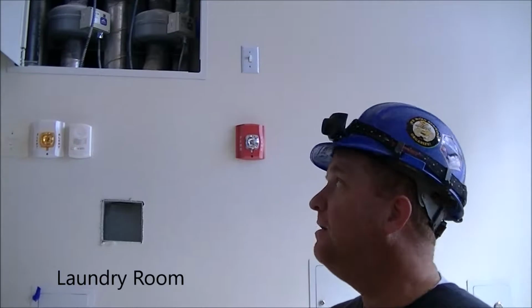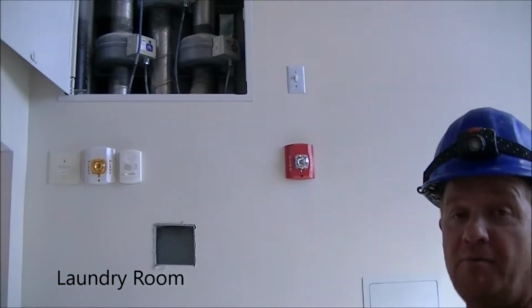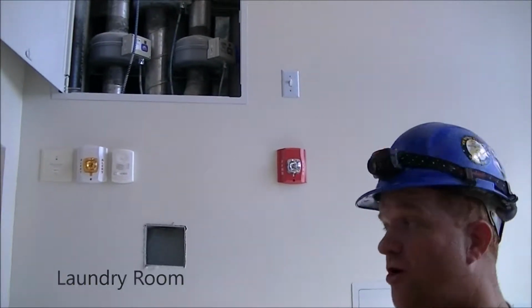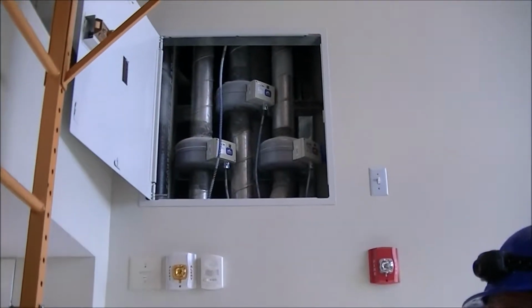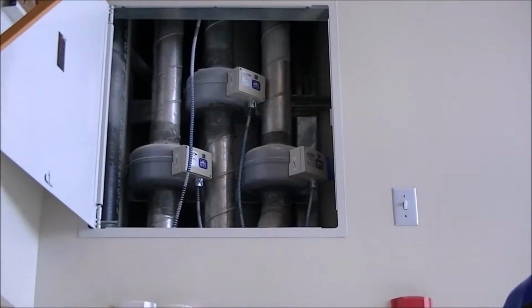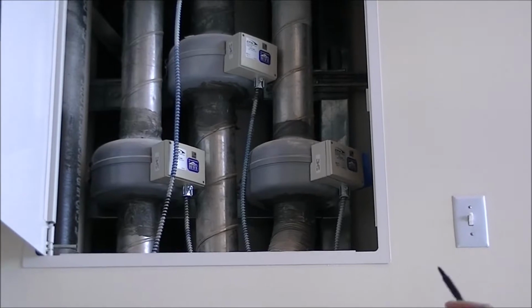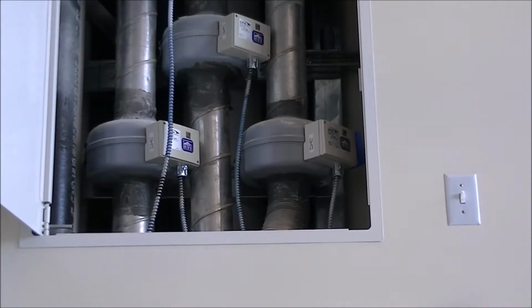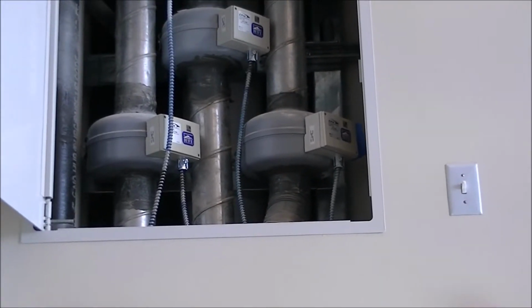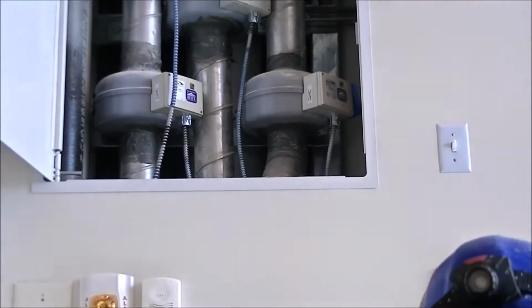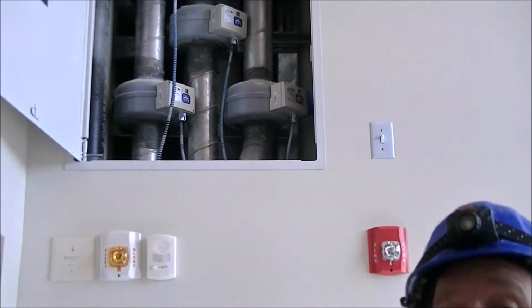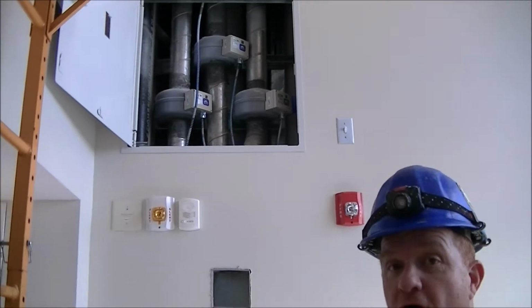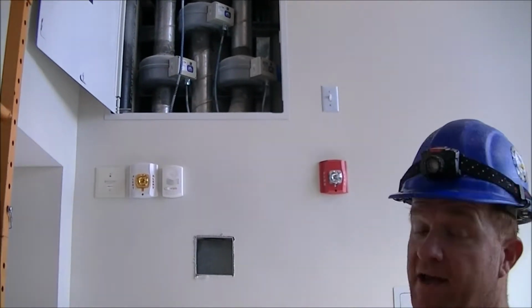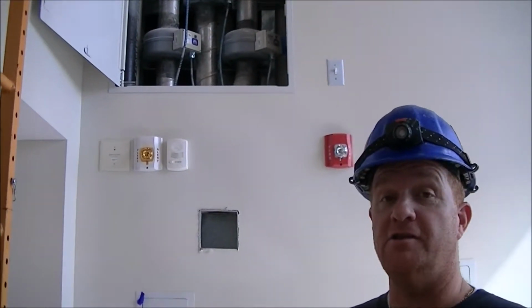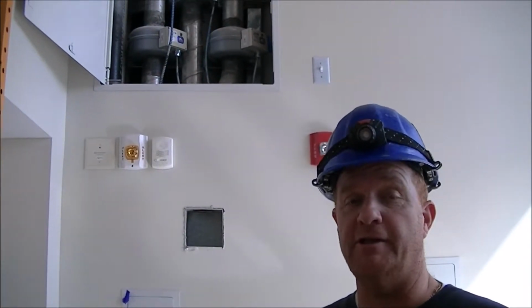So the laundry rooms on 9, 13 and 17 have a dryer booster fan set up for each dryer, just to help with the extract of the hot air. So you've got 3 fans, 3 dryers, 1 per dryer. They actually operate as soon as the dryer sees any load, so they are worked via a current transformer. So as soon as the dryer runs, the associated fan will run with that dryer. This is typical on floors 9, 13 and 17.